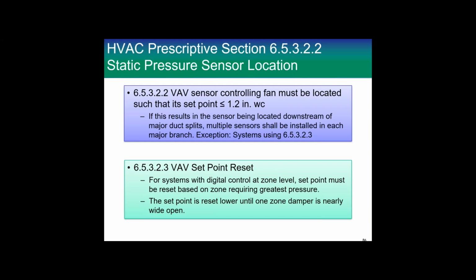It's a place to start, because what you have to do after that is, for systems with digital control at zone level, set point must be reset based on the zone requiring the greatest pressure. The set point is reset lower until one zone damper is nearly wide open. So what this means is that your digital controls are looking at each damper in each one of your VAV boxes. And if one damper is all the way open and still cannot satisfy the space, then you have to speed up the fan. If none of your dampers are fully open, then you can keep slowing down your fan. So your sequence of operations has to talk about, if no dampers are fully open, my fan keeps slowing down until one is 100% open, and then it has to start speeding back up.